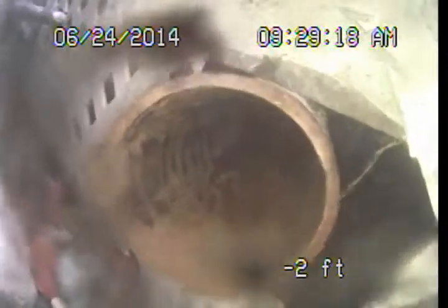Coming back around the corner here, I wanted to just take a quick look. Yeah, we're all coming up the same pipe, so we're kind of pulling back towards the building here. Now we're coming up out of the clean out. And the thing that's funky about this clean out is normally you drop straight in just from here, but this is under the deck, so they've extended a pipe out and over. We're essentially just right here, just coming outside the deck, so a little unusual, but certainly I don't see any reason to recommend changing anything.